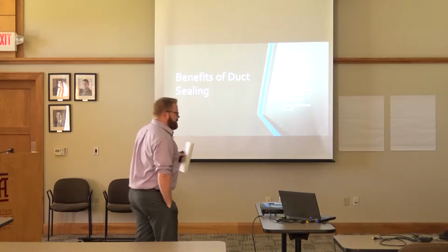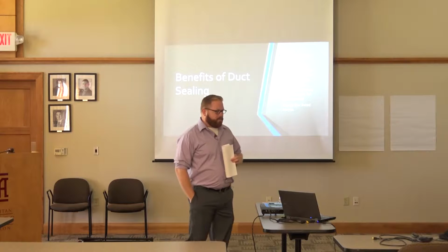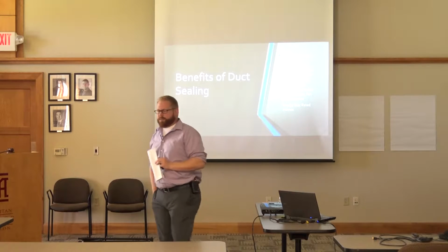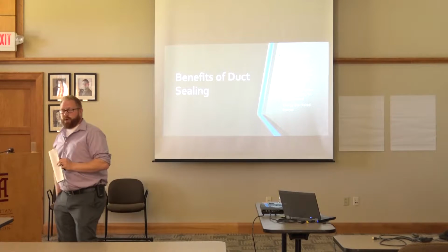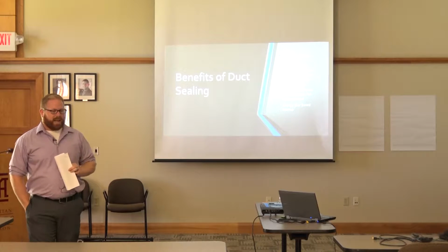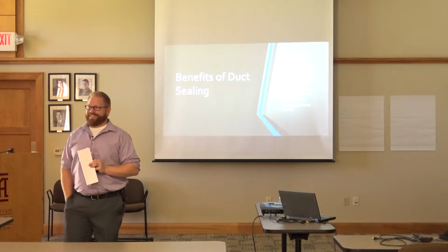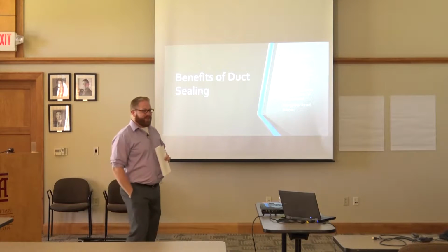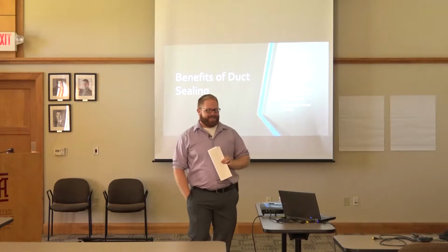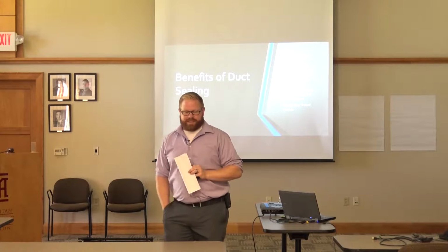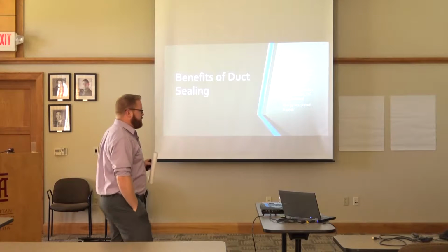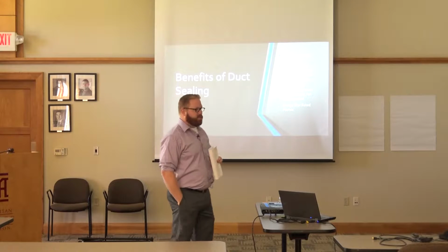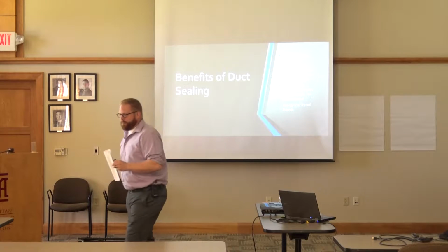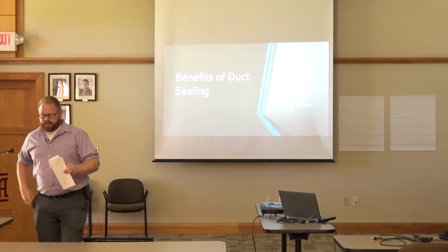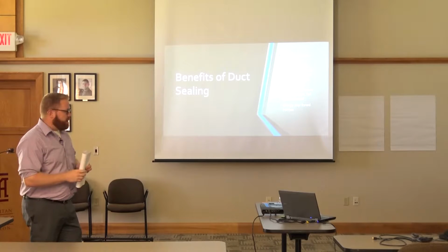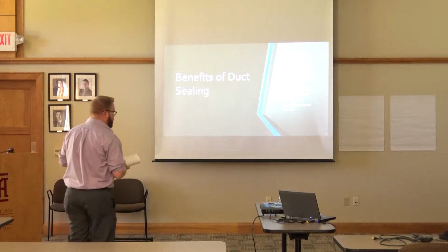There are different ways to tackle duct sealing. The most common is foil tape, not to be confused with duct tape, which isn't meant for ductwork. It dries out fast and doesn't have the adhesion of an actual UL listed foil tape. Mastic is another option for duct sealing.